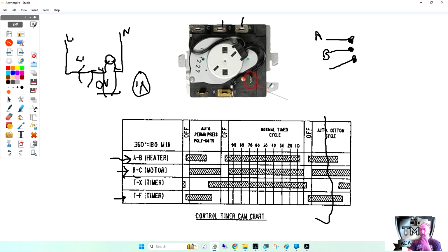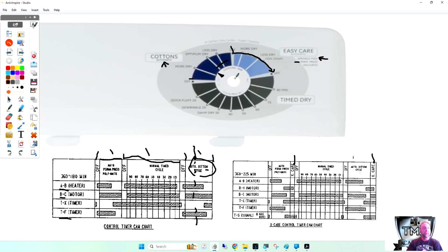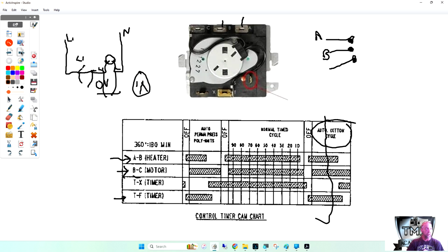But the other information I was really looking for was, if I'm telling someone to check that switch on the timer, you have to be in the cycle. You have to have this dial pointing where that machine's not working. If it's automatic or timed or whatever, I have to have it in that cycle when I'm checking that switch. I can't have it in the off position, because in the off position, heck, the switch isn't even closed. So you have to have it in the cycle, and that's the important thing to do so you don't get it wrong.